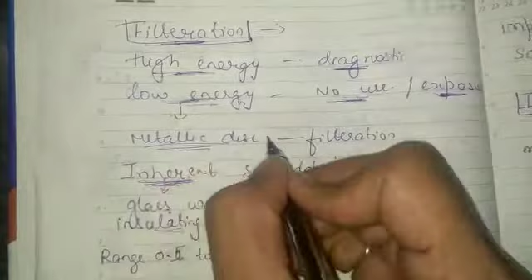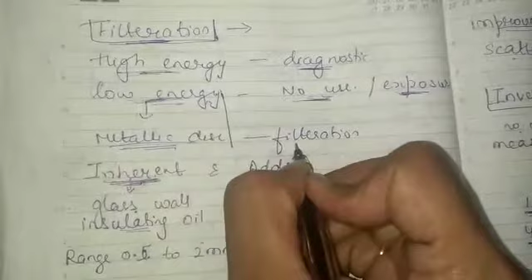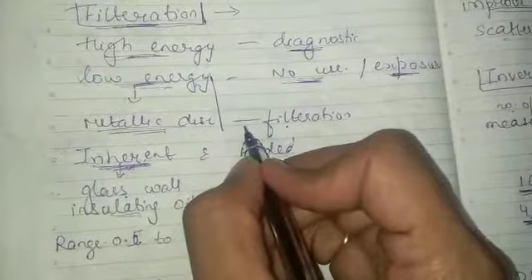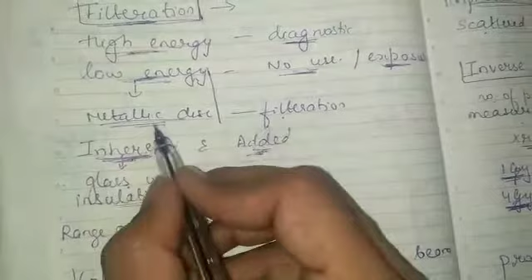Filtration is a metallic disc and it will restrict this low energy. It will stop these low energy photons. So this is filtration. The filter will be in the beam path, and it will remove all this low energy radiation, so that high energy photons are able to contribute and make an image.